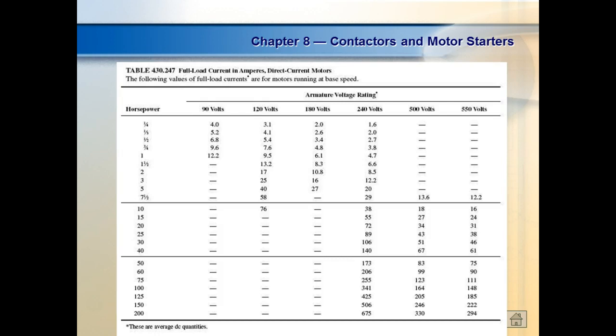This gives us typical full load current of different motors running at different voltages if I don't have the nameplate, if the nameplate is gone off the motor. So a 2 horsepower DC motor running at 240 volts, I should expect it to pull 8.5 amps or so. Does that make sense? You okay? So this is a little better than the one in the book. The one in the textbook is a little hard to figure out. This doesn't give you all the different speeds.